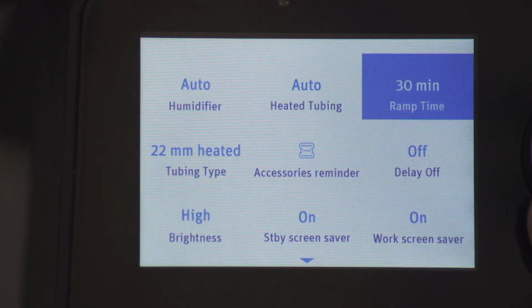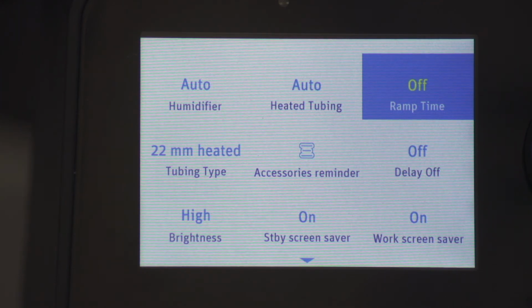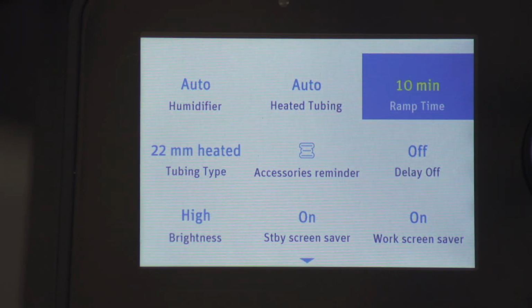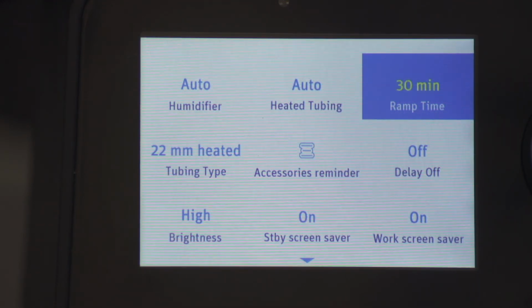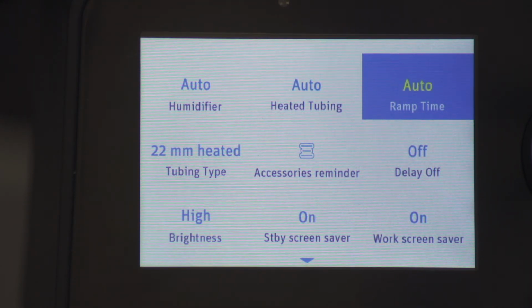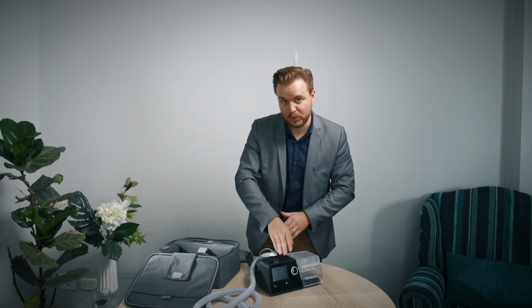Ramp time on this device, you can ramp up to an hour. So the time it takes you to get to sleep, you set that accordingly. If it takes you longer, usually when you're using CPAP, set it a bit longer than you would normally take to get to sleep. Just come in here and set that right down to off if you don't want any ramp time, 5 minutes, goes up in 5-minute intervals. You can also have the option of setting the ramp time to be automatic. When ramp is made automatic, the device will detect when you start to get into a light stage of sleep, or if you start having events, if you start experiencing any apneas, the device will start increasing the pressure from there accordingly. So that's when it's set automatically.